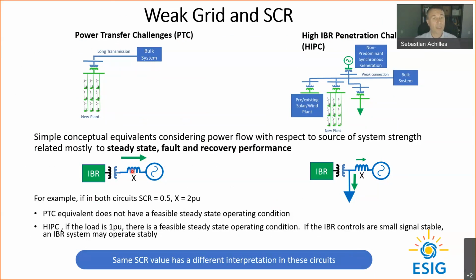We'll have the inverter-based resource connected through a large reactance to a source. This will be the Thevenin equivalent. In this case, the equivalent I'm proposing is kind of the same, but it has a load. And this load has the effect that the generation of the inverter-based resource is partially consuming the load and is partially transferred through this reactance. In the case on the left, all the power generated by the inverter-based resource is transferred through the reactance. Now, speaking of short circuit ratio and how it affects this problem, the short circuit ratio, as it's usually defined, is the ratio of the short circuit level at the terminals of the inverter-based resource divided by the rated megawatts of the inverter-based resource.